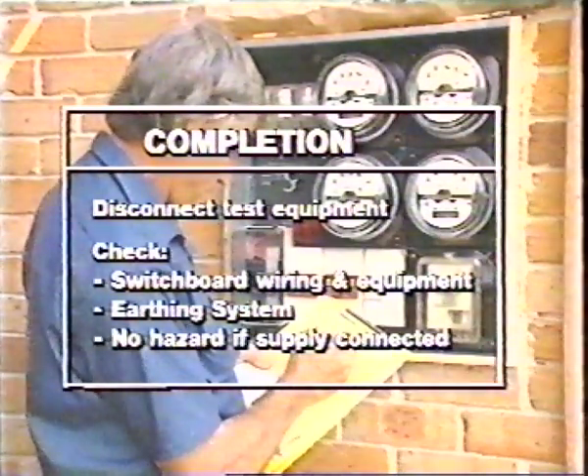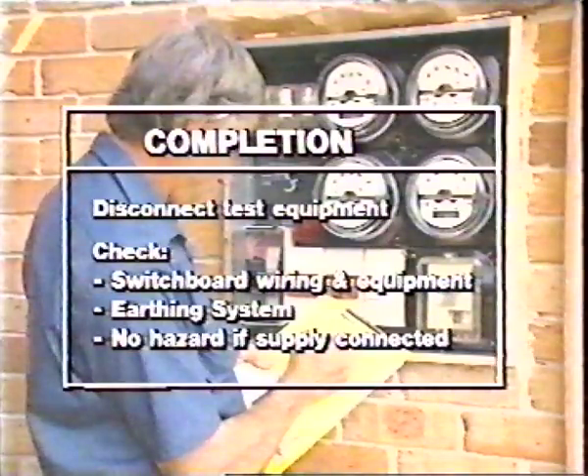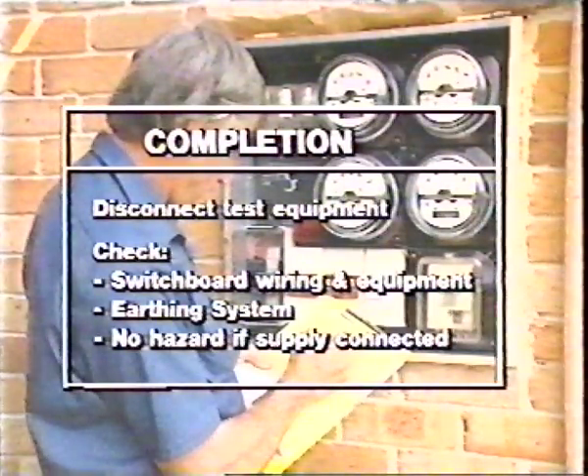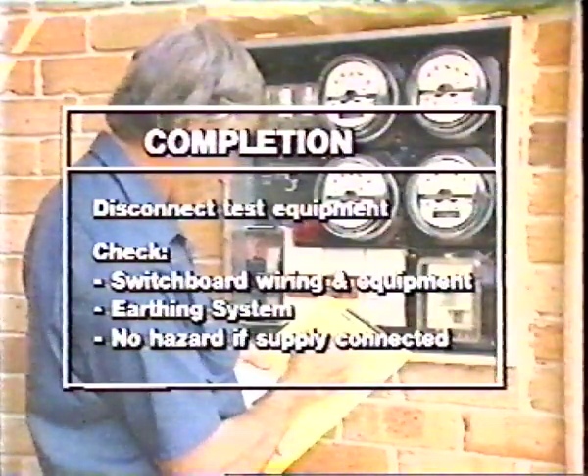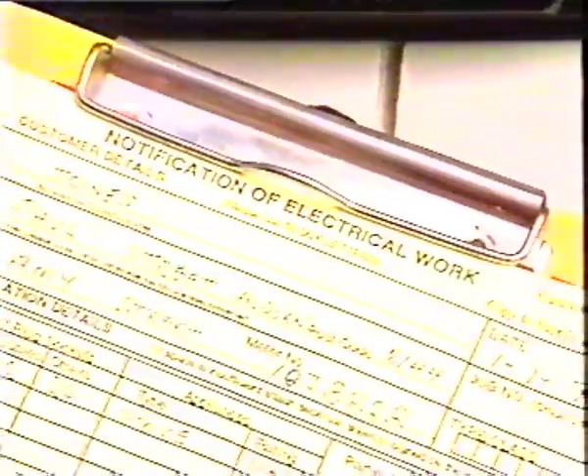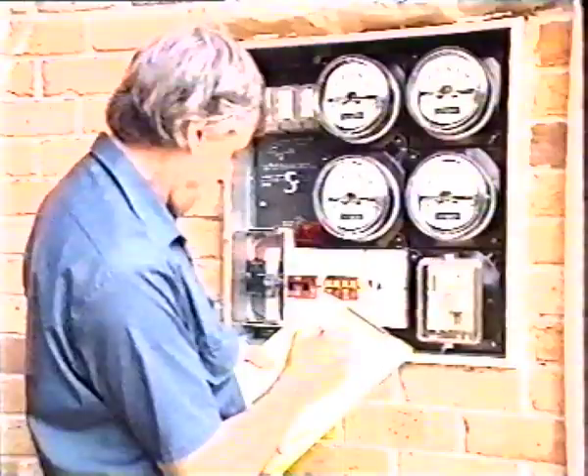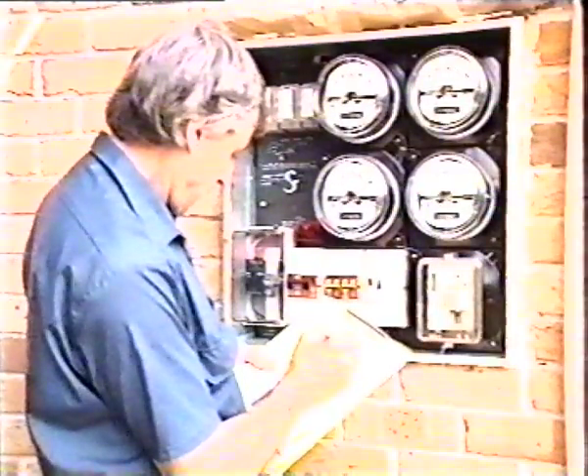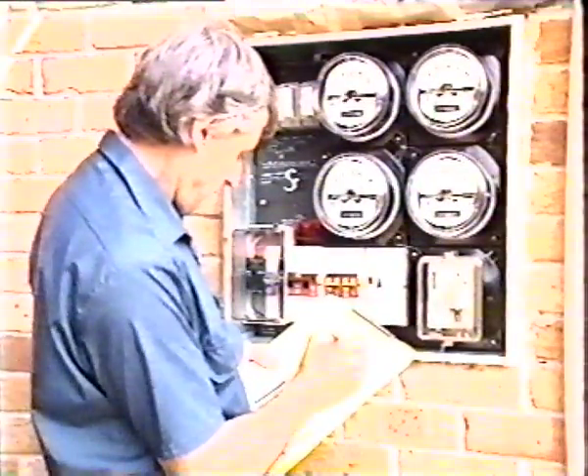Then, check switchboard wiring and equipment and the earthing system to ensure that there will be no hazard when supply is permanently connected. Finally, complete the notification of electrical work form. This form is in triplicate, and you're required to submit 1 copy to the supply authority, 1 copy to the customer, and retain 1 copy for yourself for a period of 2 years.